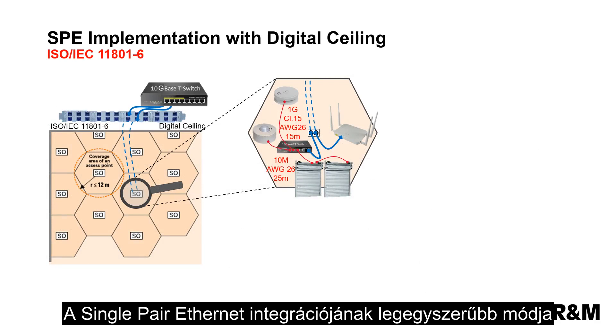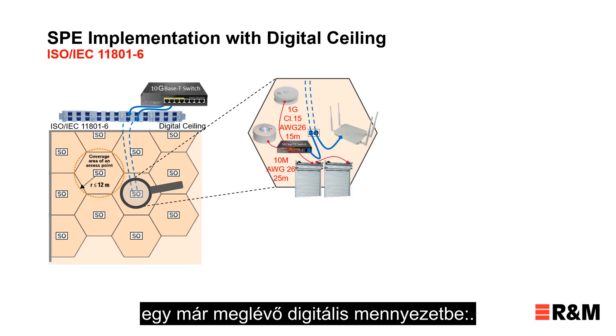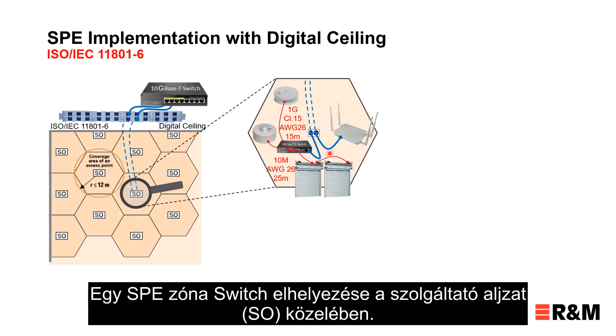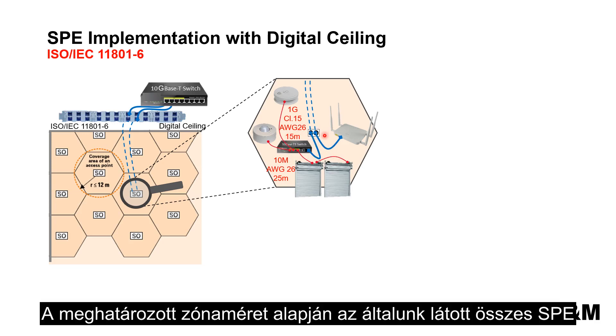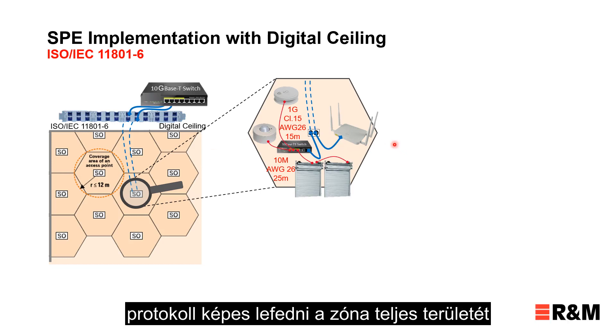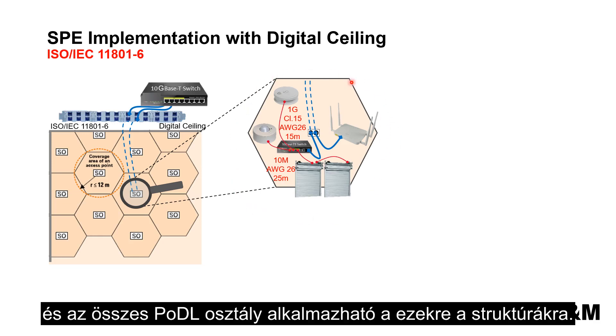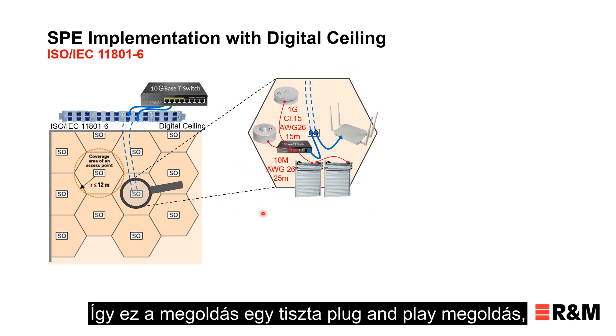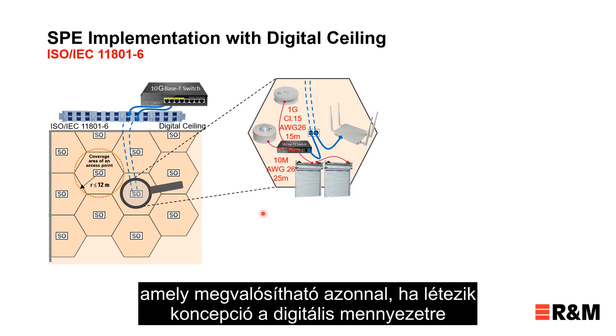The easiest way to integrate single-pair Ethernet into an existing digital ceiling is to place a single-pair Ethernet zone switch near the service outlet. Based on the defined zone size, every single-pair Ethernet protocol we have seen would be able to support the complete range of the zone, and all PoDL classes could be applied in these structures. This solution is a pure plug-and-play solution that could be realized immediately if you have a digital ceiling concept.